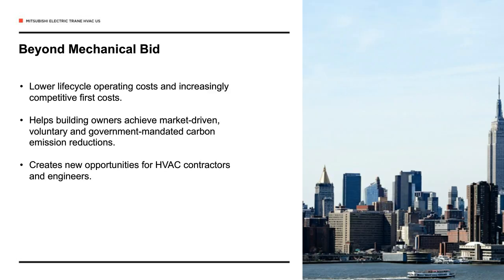Now let's talk a little bit about going beyond the mechanical bid. VRF installed costs have come down significantly in recent years. However, first costs can sometimes be an obstacle to installation. If you look exclusively at the mechanical bid, that certainly becomes apparent. A developer or building owner seems to pay a premium to install VRF systems over a VAV or other conventional systems, for example. But if we look at going beyond the mechanical bid and how the characteristics of HVAC systems affect the cost for other components of the building like plenums, ductwork, and structural steel, we start to see how even the first costs of VRF systems can be competitive with less energy efficient alternatives. For example, eliminating the need for long runs of ductwork.